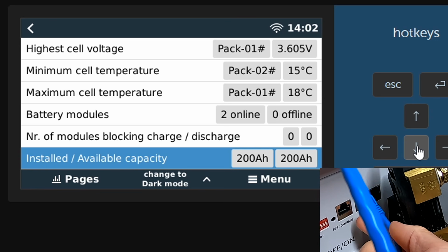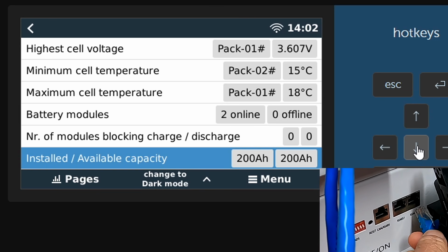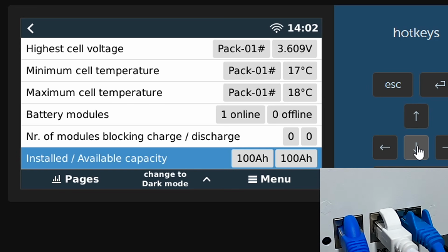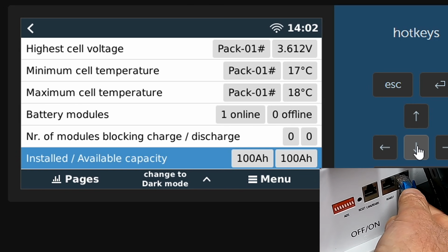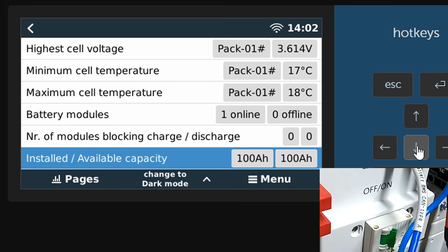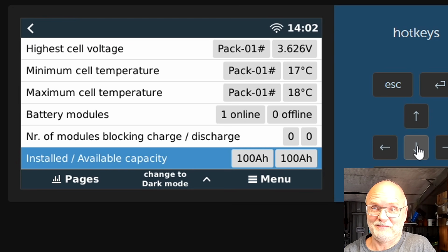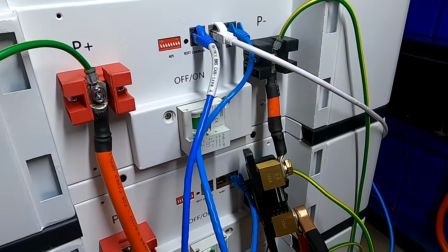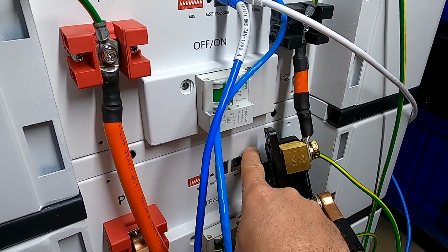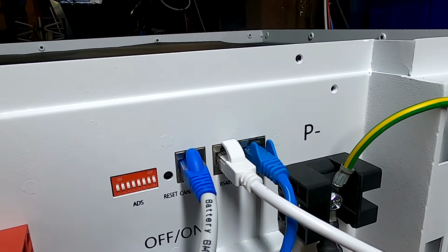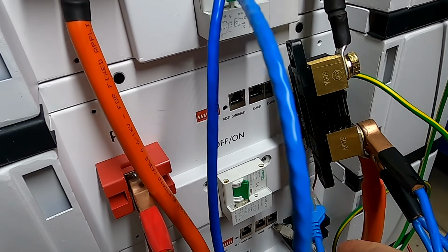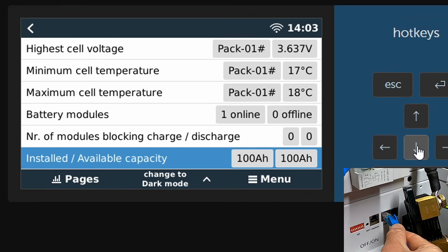What happens if we take this cable and plug it into the second port instead? From port number 2, this blue cable goes down into port number 2 of the next BMS. We can see it's not working. So these ports are actually not in parallel in the SEPLOS BMS because of their automatic configuration - it needs to be 2 to 1, 2 to 1. They explained this has something to do with the automatic addressing of these batteries. So since we're in port number 2 with the blue cable, we need to plug it into port number 1 down here.